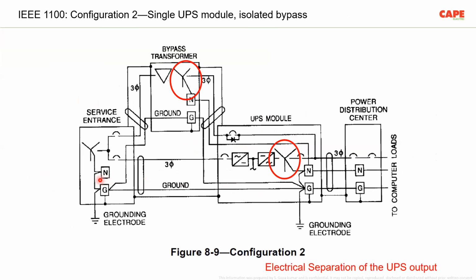Here is another configuration of UPS, a single UPS module with isolated bypass. Of course, there is an isolation transformer on the bypass circuit. Here you can see the transformer is a delta-star transformer and the star point is grounded. Now, this grounding is coming, and you see the UPS also has an electrical separation. The neutral is connected to earth. Inside the UPS, the neutral is connected to the earth. Where I am scrolling and showing the pointer, that is neutral earthing. It has nothing to do with the earth pit.